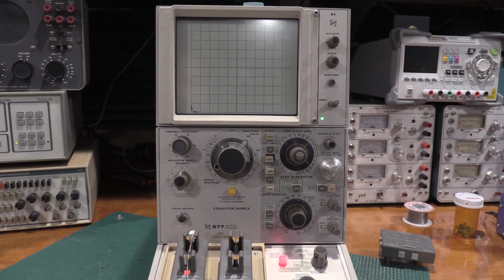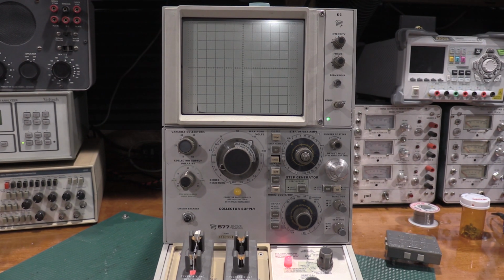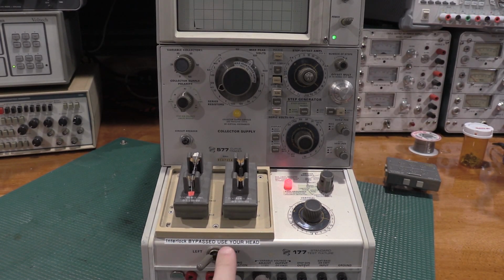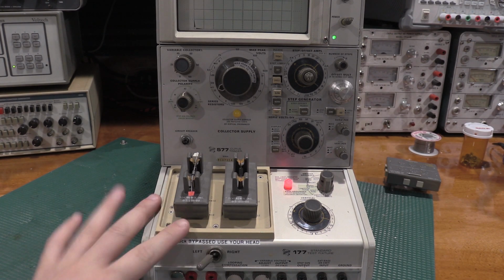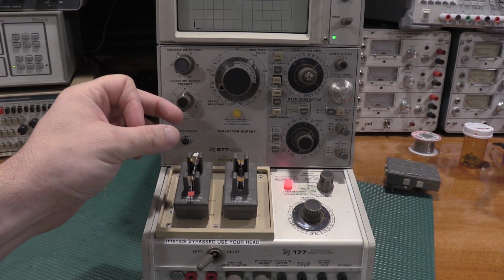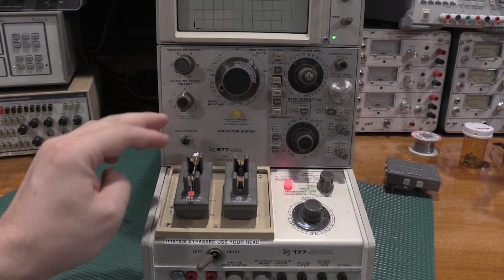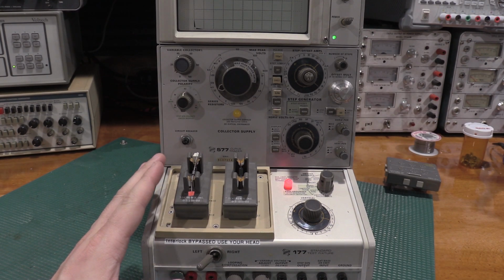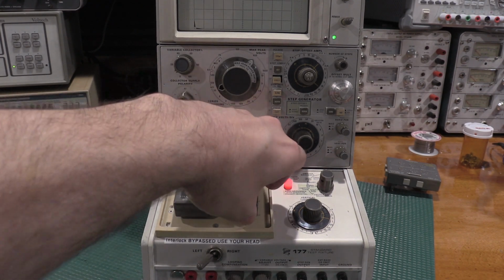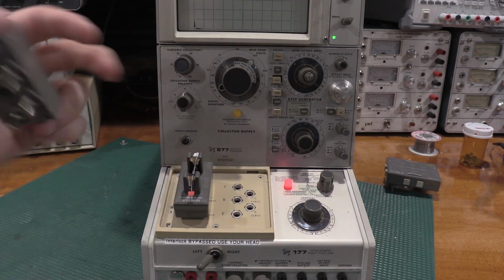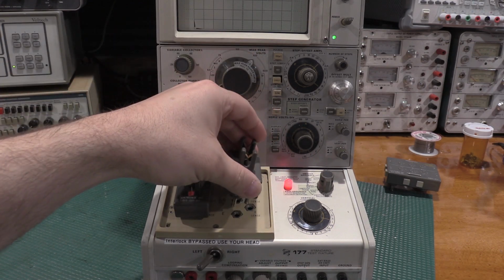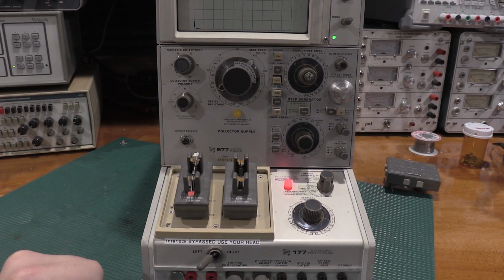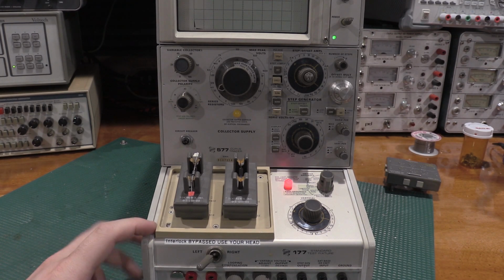Okay, I have the curve tracer moved off of the monitor power supply back onto the regular mains voltage. Everything's working. I have bypassed the interlock, the use your head, heed the warning, between the collector and the emitter pins on this test fixture, which is the same for up here, because these are 2-terminal Kelvin sensing fixtures. They have 4 pins on the bottom, so they have C, E, C sense, and E sense. Because these are for testing 2-terminal devices, they don't need the base connection.